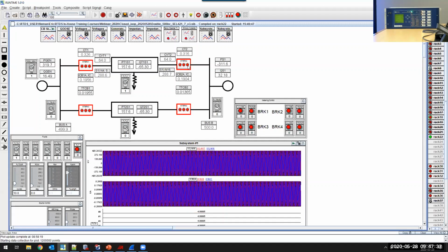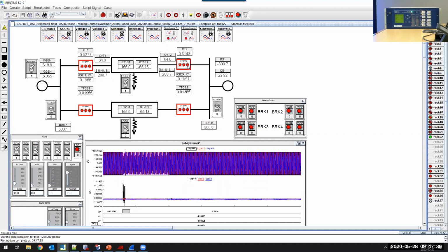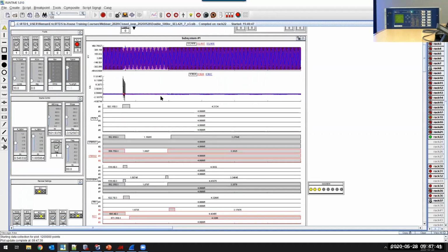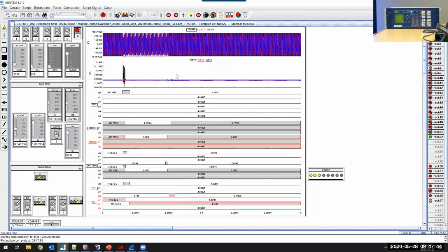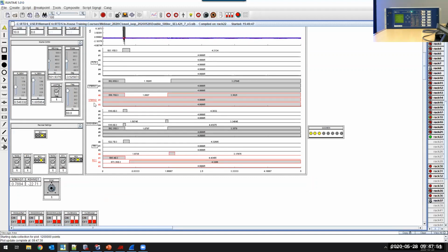Okay, so that's expected. A phase was open and then reclosed, and we can have the parameters of interest monitored in runtime here as well. We can see the A phase primary side current. And from the breaker status here, we can tell the breaker 2 A phase is open and then reclosed. From the incoming GOOSE messages, we know that the first bit is A phase trip, so that's correct. Then the reclose comes in here, and this is the permissive trip. Ignore the other three, these are for debugging.